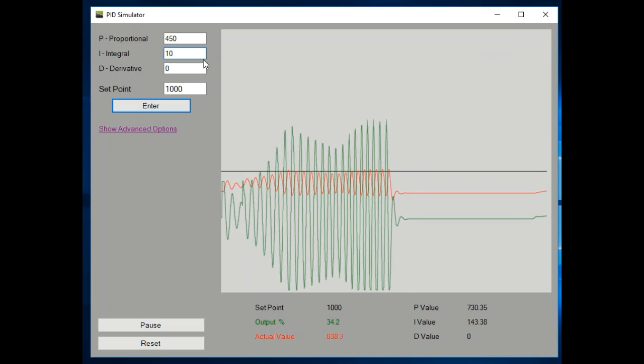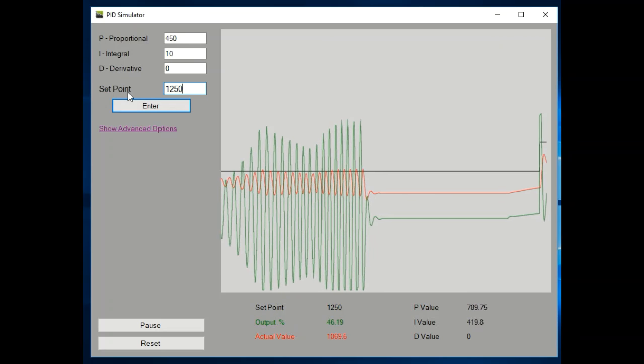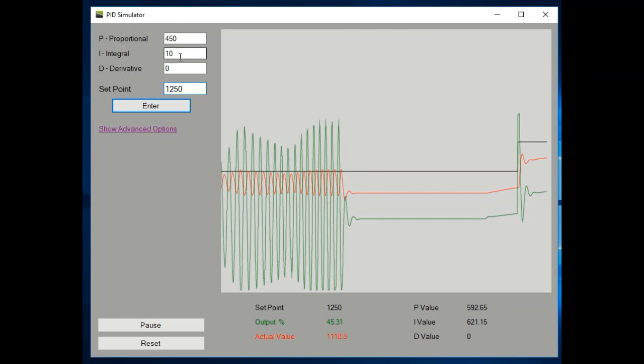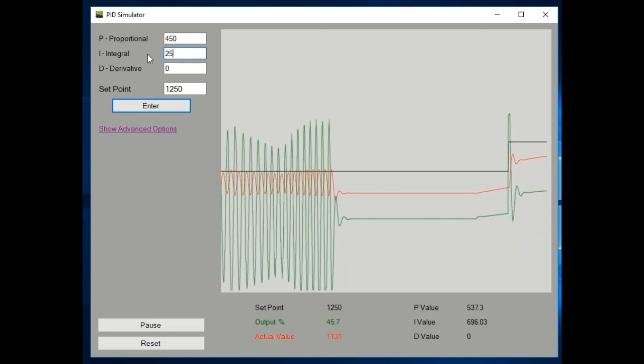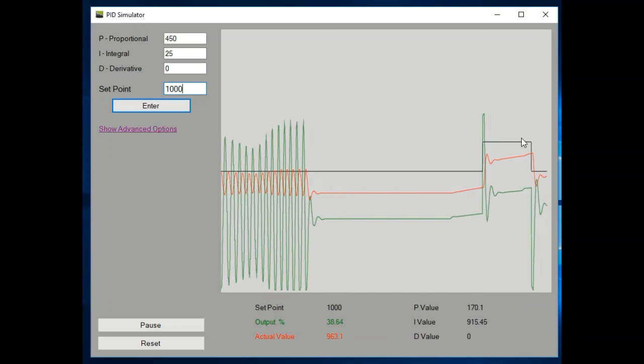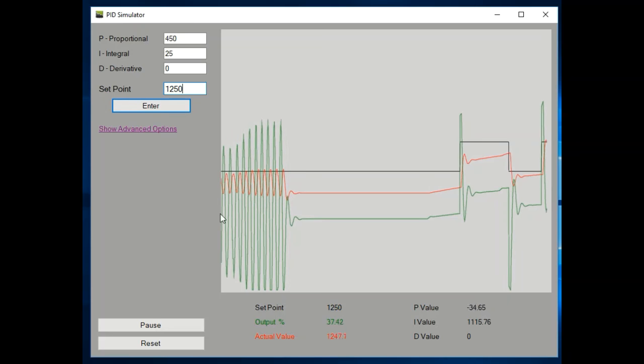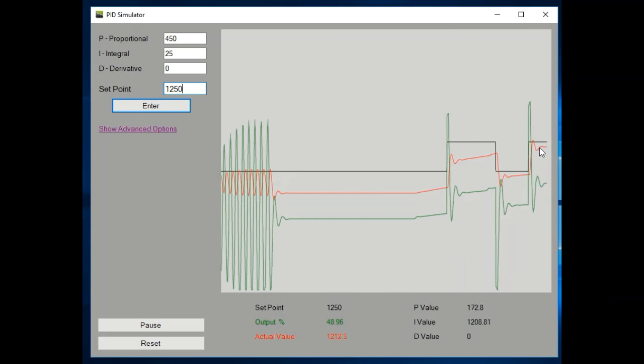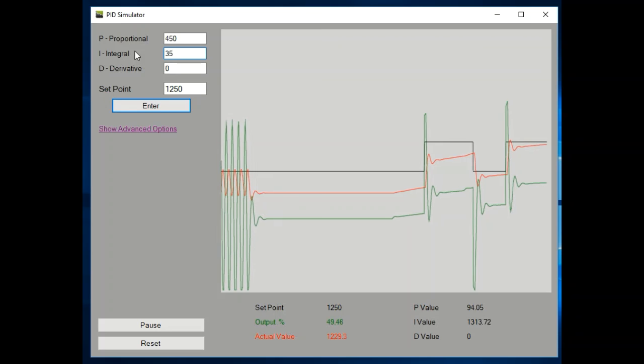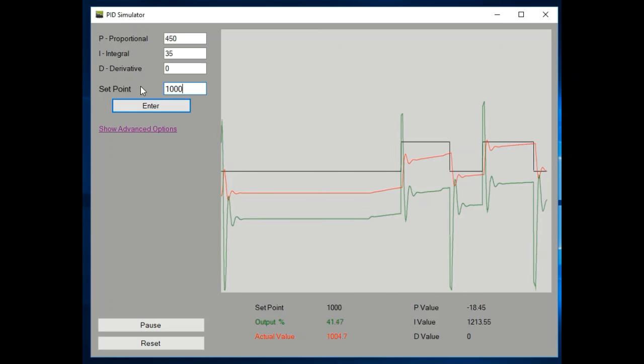The idea when tuning the integral value is to slowly increase until you have a reaction time that you like. So let's change the set point, watch our reaction, and adjust as necessary. I'm still not reaching the set point, so this integral is far too low. Bringing the integral up — now I have some overshoot on the set point, but still a little bit slow to reach where I want to be, so I'll continue increasing this.